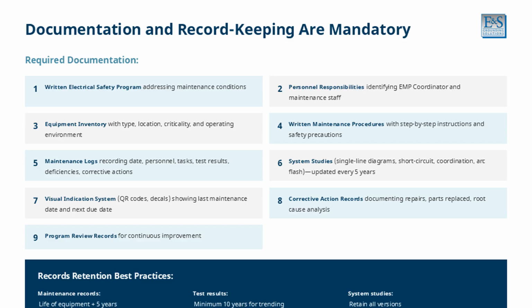Documentation and record-keeping are mandatory, with no exemptions for small companies. Required documentation includes 9 elements: a written electrical safety program addressing maintenance conditions, personnel responsibilities identifying the EMP coordinator and maintenance staff, an equipment inventory with type, location, criticality, and operating environment, written maintenance procedures with step-by-step instructions and safety precautions, maintenance logs recording date, personnel, tasks, test results, deficiencies, and corrective actions.